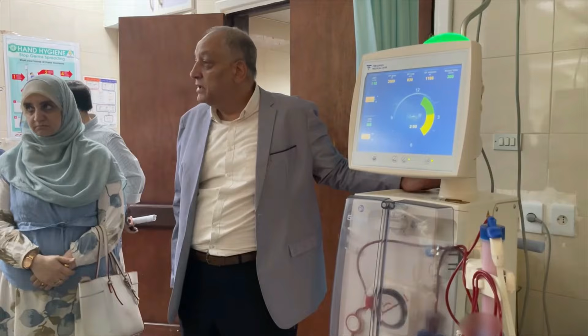This is what's called, in hemodiafiltration, a two barrier system, because you are using two endotoxin retention filters behind the machine. Some other machines use a three barrier system, which means two endotoxin filters behind and one disposable filter in the tubing of the substitution line. Exactly, this is the Baxter way.